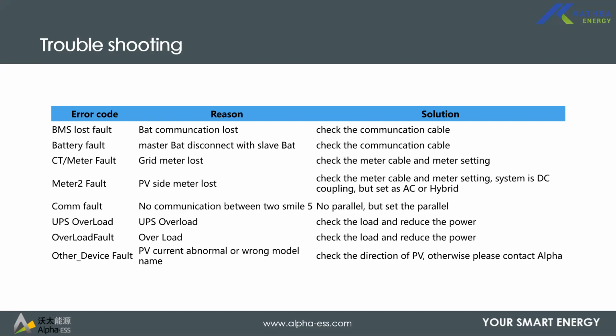And when the system loses communication with the battery, it gives a BMS fault, and if the system loses the voltage from the battery, it will give a battery fault. It usually gives an other device fault if the PV is abnormal. If any of the strings short to ground, or the voltage is above the rating, or the PV voltage is erratic, spiking up and down, that's when it will usually give an other device fault. You can also get this fault if your isolation, that is your grounding and all that of the system, gets too low, meaning the isolation resistance gets too low.